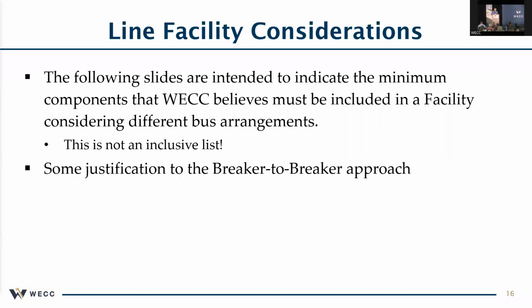So the next few slides I've got are going to show a few configurations and some thought process, and I hope it kind of justifies why this approach should be acceptable and why it works and helps. Even though you could say, well, I disagree, I think that I want to make my bus a different facility. And the problem is then we would have to go sample every piece of your bus in order to find out what those facility ratings are. So that's why we're approaching this way, and hopefully it will give a justification to our breaker to breaker approach.